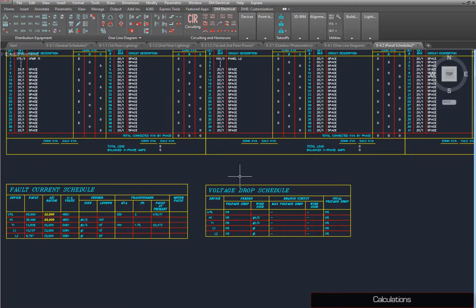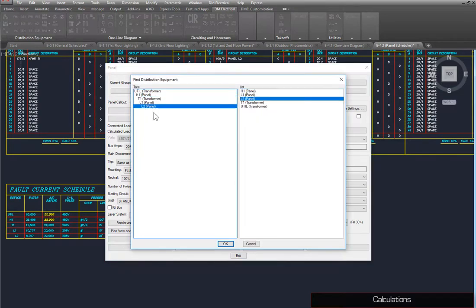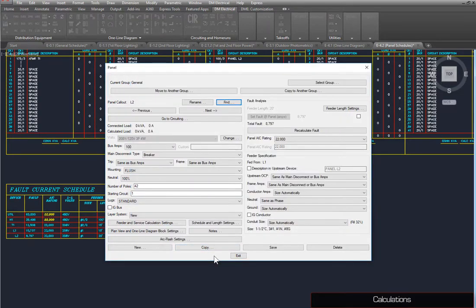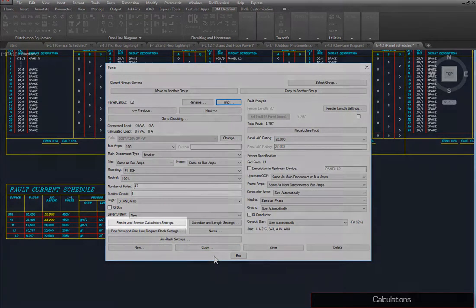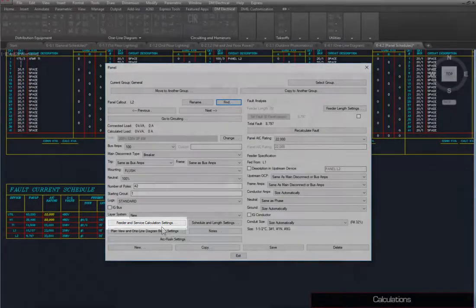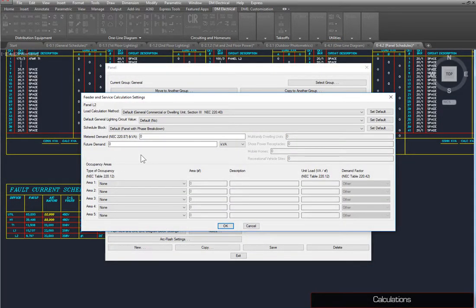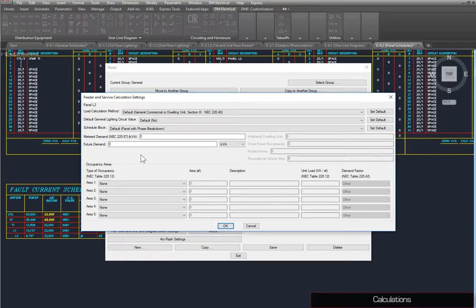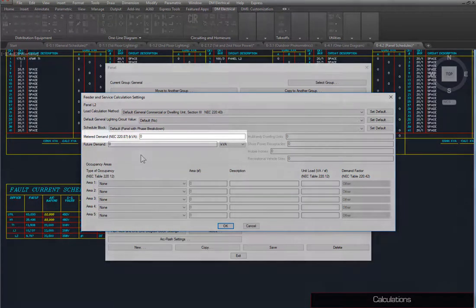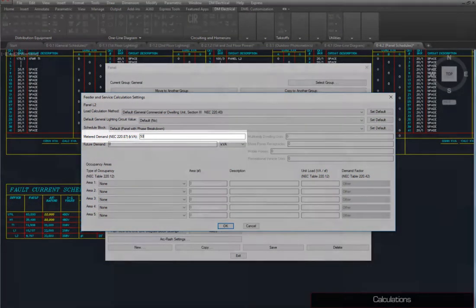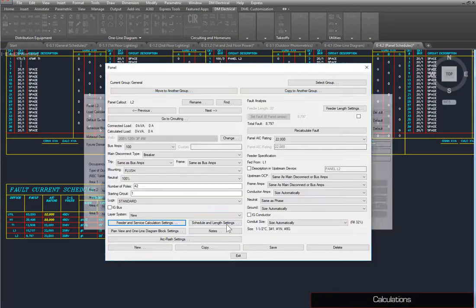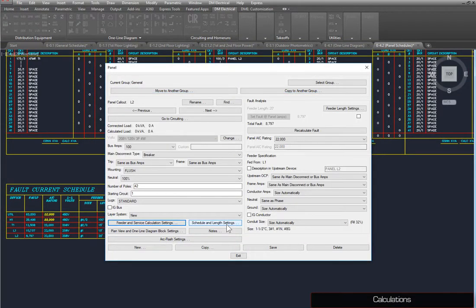To set loads, run the Panels command, and select L2. Press the Feeder and Service Calculation Settings button. This dialog box allows you to set calculation methods, demand values, and occupancy areas for calculating loads on the panel. Set Metered Demand to 50. Press the OK button. Then close the dialog box.